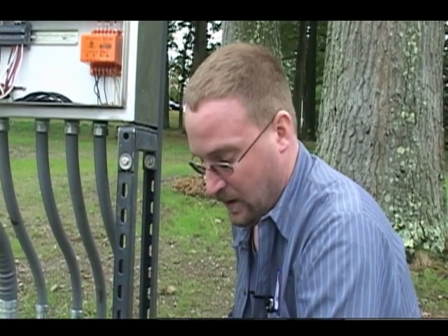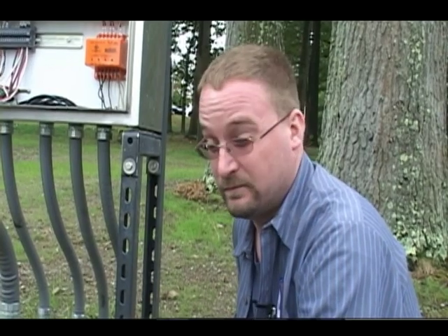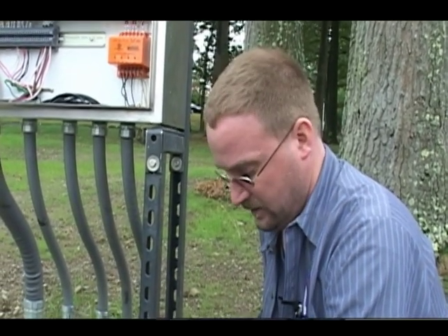Other than pulling it up once a year to check the pumps, these pumps are maintenance free. Just ignore them unless the alarm goes off. When you look down, you want to just make sure the pumps stay submerged underwater. You don't want to run the pumps out of the water for any length of time. You also don't want to constantly be drawing air into the bottom of them. So test the float system, make sure everything works, keep the water in the pit.